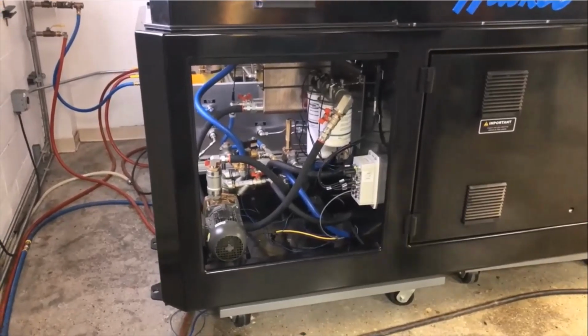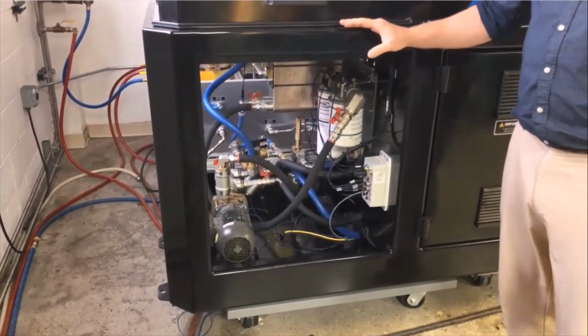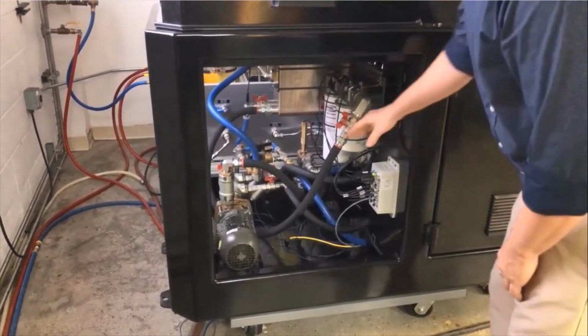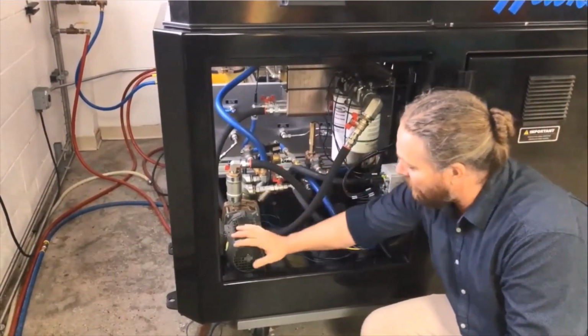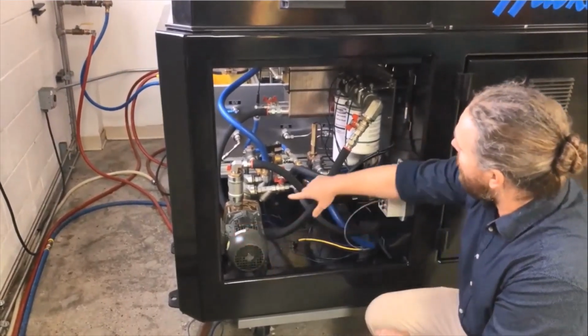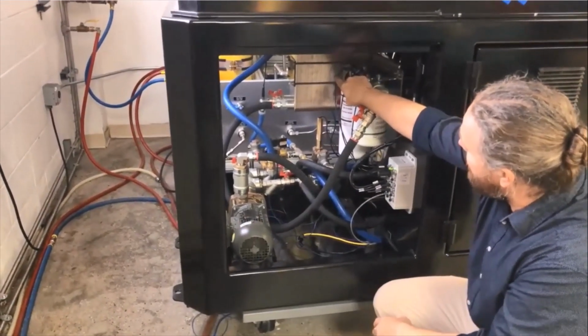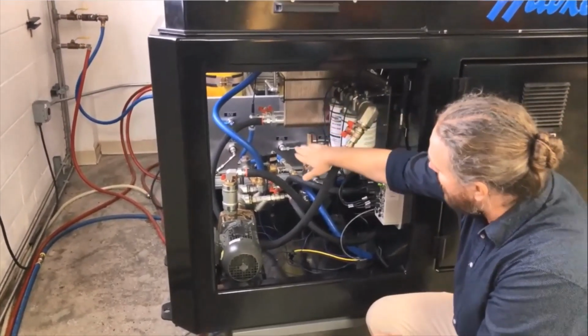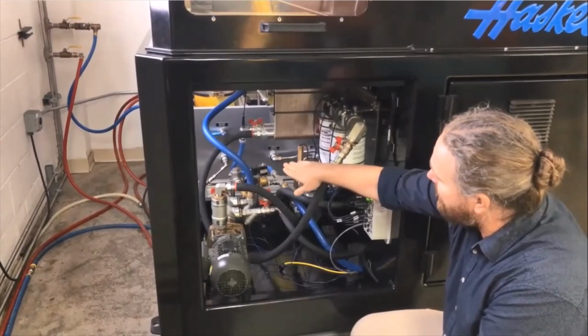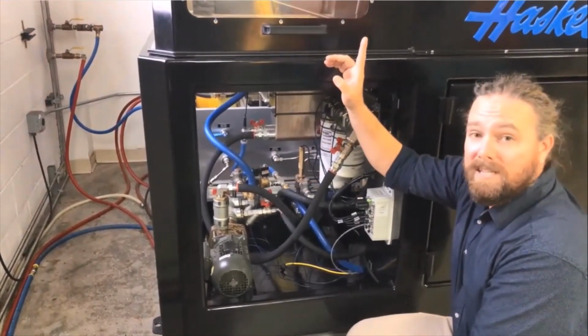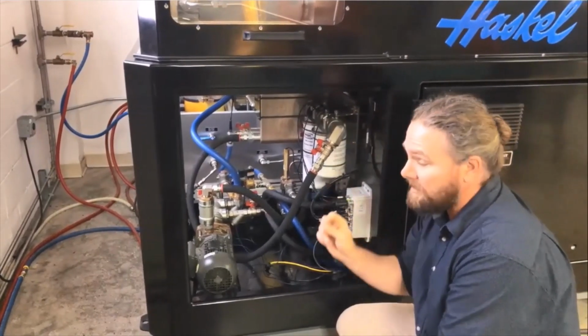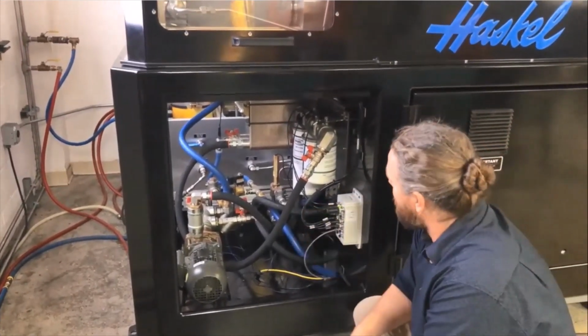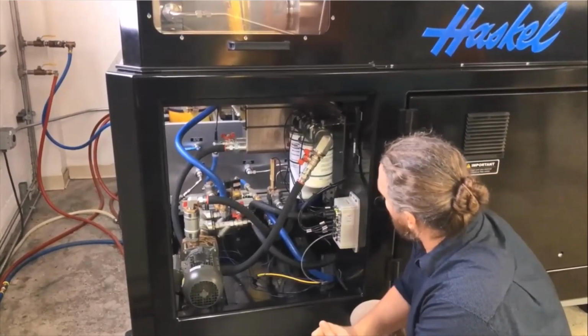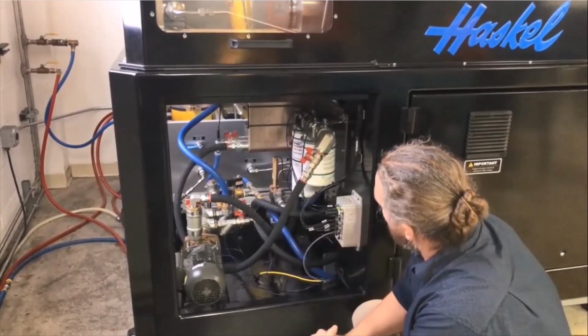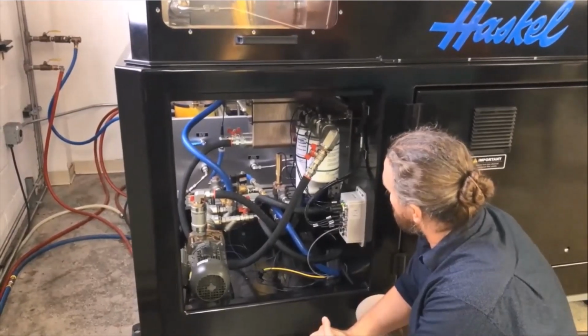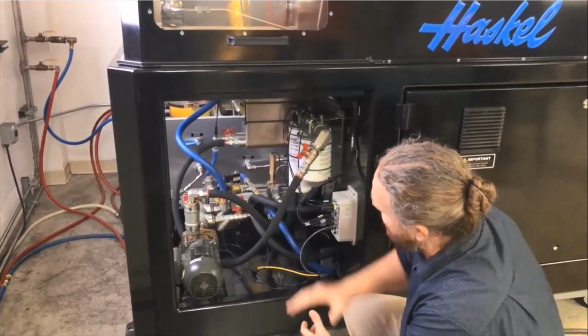The servo drive is lubricated with a synthetic gear oil, and that also provides cooling. That is going through this lubrication circuit, powered by this 3/4 horse motor. The oil is cooled down at this plated heat exchanger, and the coolant is diverted by these smart solenoids, either bypassing the coolant to go directly to the gas sections or keeping the oil at its ideal temp. The oil also goes through these 2 filters, and every 2,000 hours of service, you will replace the oil filters and replace the oil.